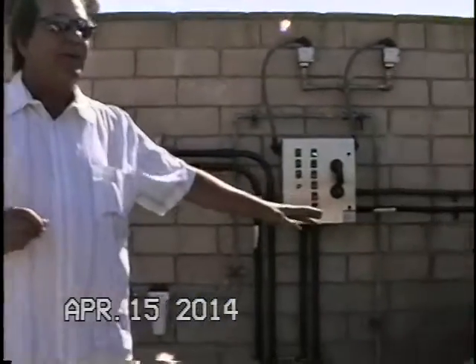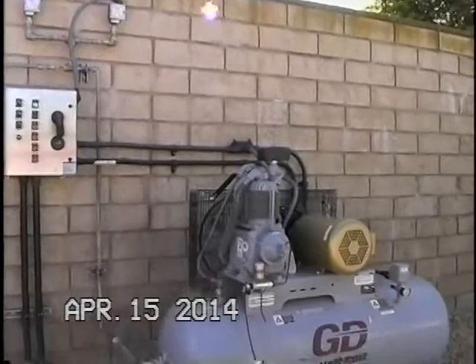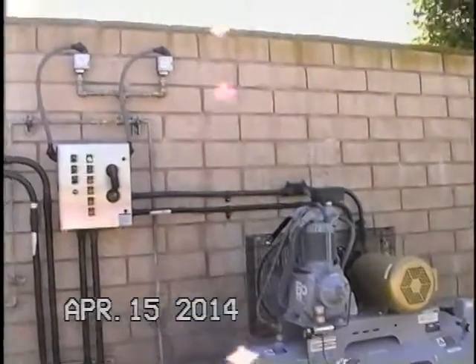So if we've got our steady state level that we're trying to maintain at 50%, if the level rises up 3 inches, after a time delay we're going to have a call for air. It'll actuate a solenoid valve in which we're going to add air, and it's going to push the liquid level back down. What happens is this compressor mainly becomes like a pump. It's not adding pressure. What it's really doing to the system is just pushing that liquid level back down. Now, the other effect is if the liquid level is too low, after a time delay, we're going to vent air, and we're going to allow the system pressure to come back up to its liquid level, and then we're going to shut it off.